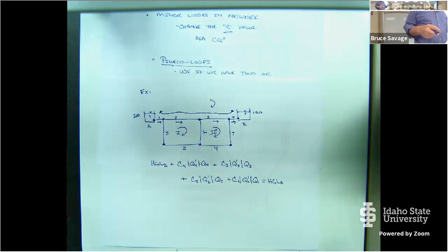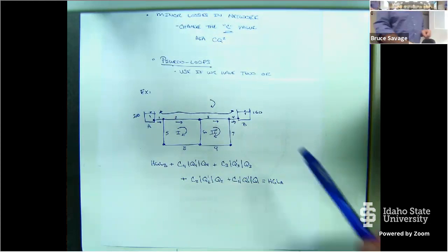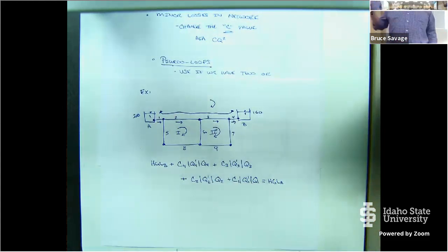First, I find the flow rates because I'm using the flow equations. Then I can go back and find the pressures, and the pressures are dependent upon those fixed grade nodes. My hydraulic grade line is known at those locations. And that's why I can start at B and go to A and say that it equals A, because A and B are known values, they are not unknown, they're fixed.